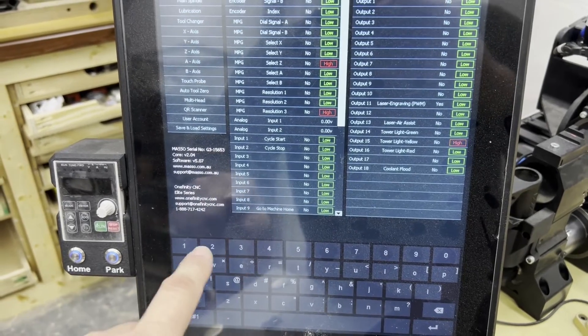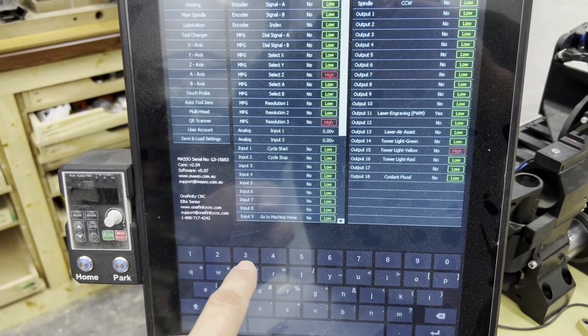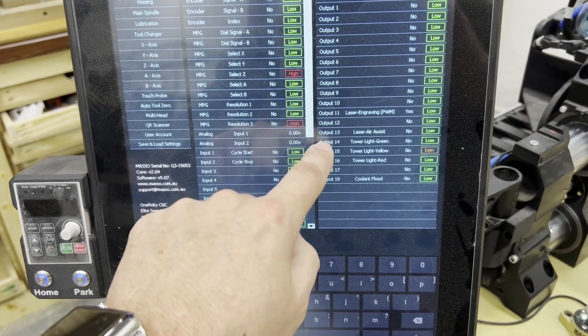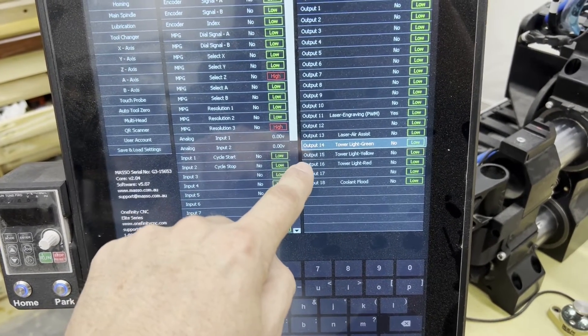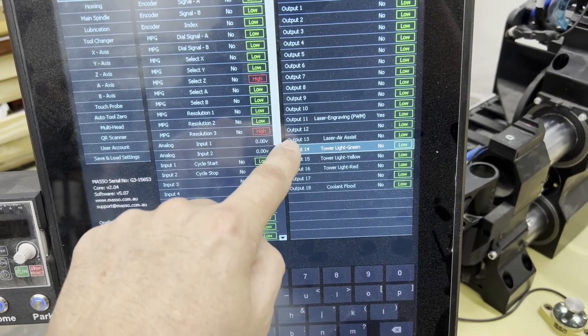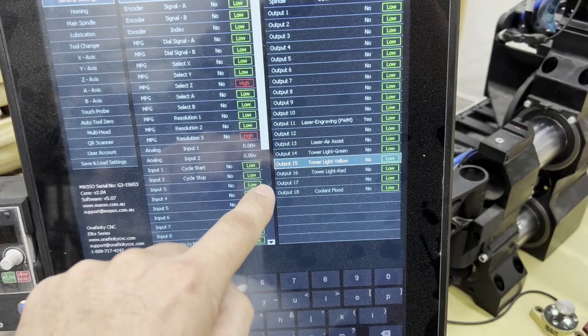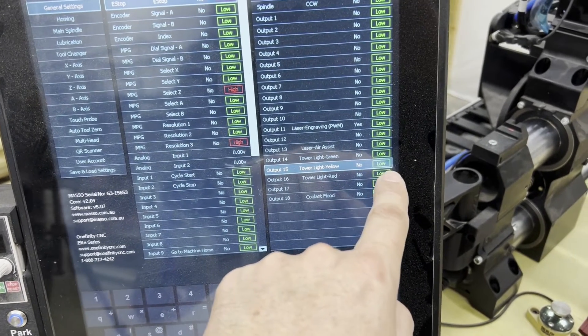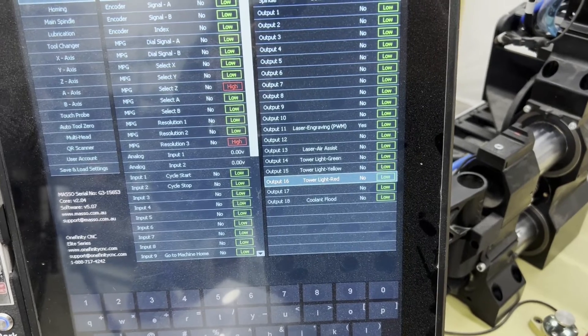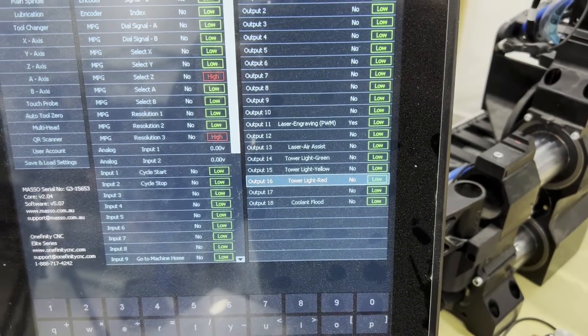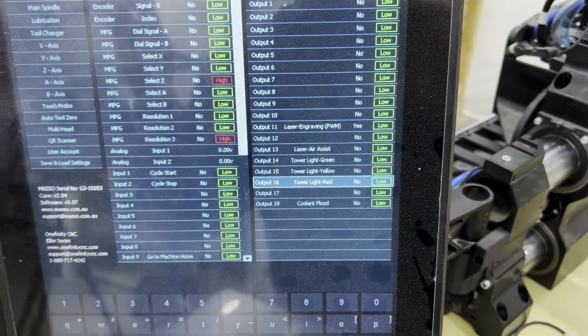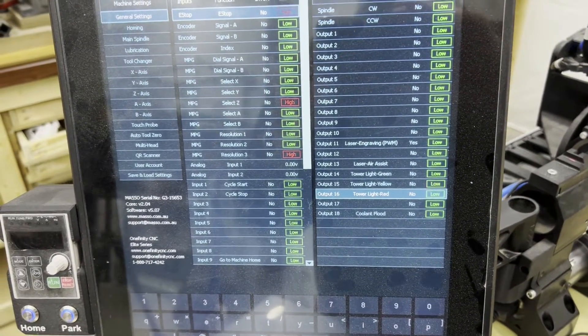But what we'll do is, we'll go to the setup, and get rid of the password. And we want to look at our TTL outputs. And we can see here, we have output 14 is set up for tower light green. 15 is set up for tower light yellow, and it's blinking like crazy right now. And 16 I have set up for tower light red. And once you get those set up, it's done. There's nothing more to it. This is a pretty easy install.